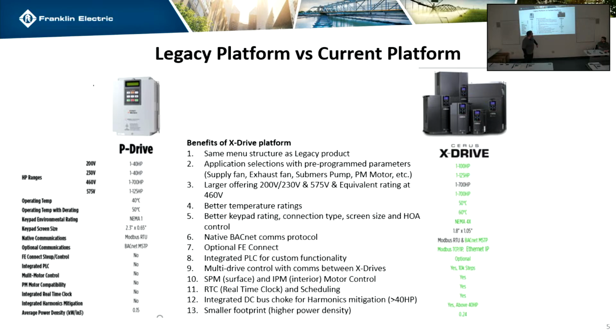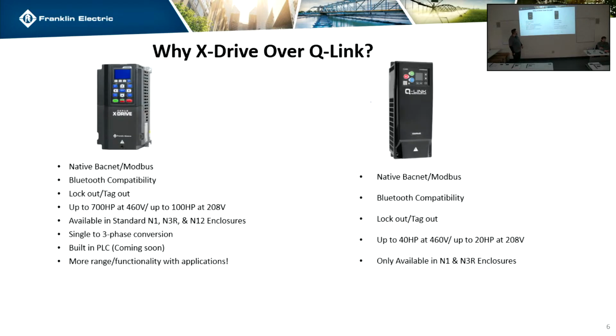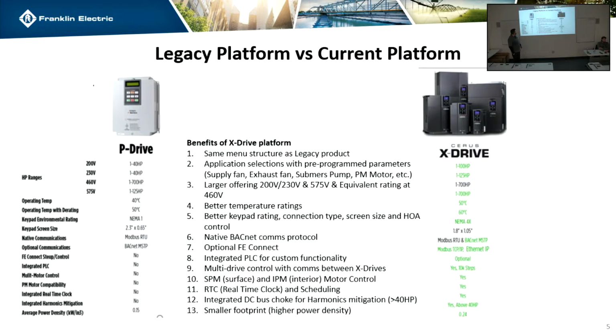Is that for the packages? So the drive itself goes all the way to 700 horsepower, and then our packages will cap out at 100 and 125, depending on the voltage. We'll go back one more real quick. The P drive did not have BACnet in it. You had to have a card, but it did have Modbus. The X drive has BACnet and Modbus built into it. We have an Ethernet IP card for Modbus if you want that, but the BACnet is the RS-485.